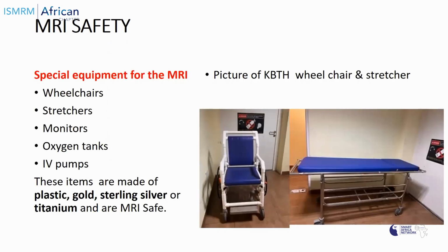Now, because of all these safety issues, special equipment for the MRI had to be used. The wheelchairs, stretchers, monitors, oxygen tanks and IV pumps should be made of materials that are safe, like plastic, gold, sterling silver, titanium, and others. This is a wheelchair that we use in the MRI unit of the Korle Bu Teaching Hospital. It's titanium, a metal covered with plastic, MR safe. And then this is a special dedicated trolley we also use for the MRI. So patients that come at zone 1, after screening, we transfer them onto this wheelchair or the stretcher before they even get to zone 3, 2, and even 1.